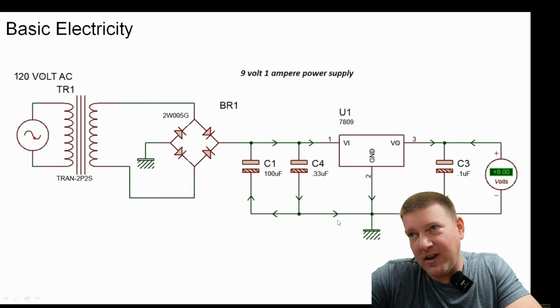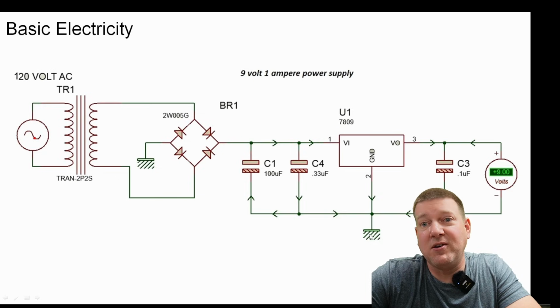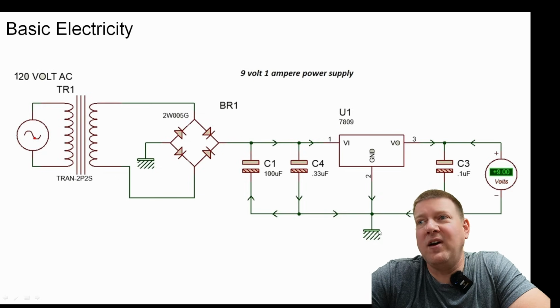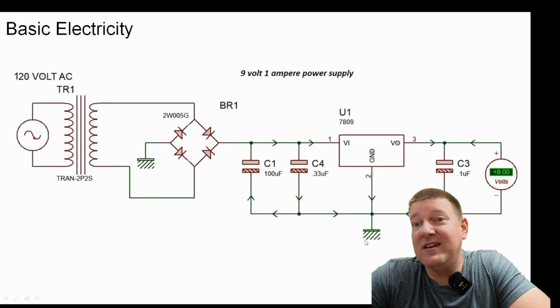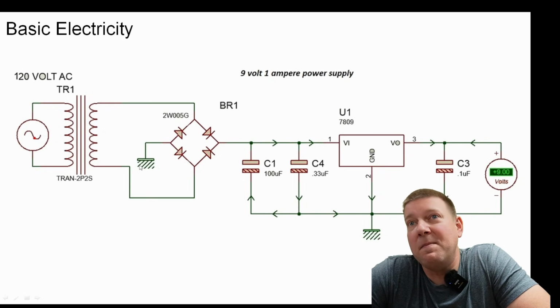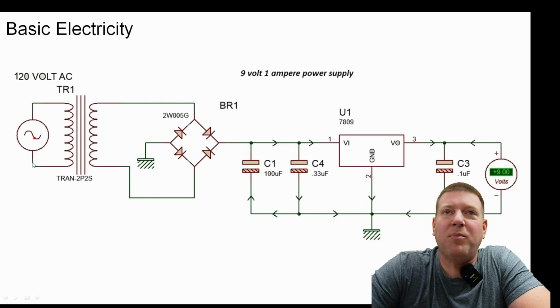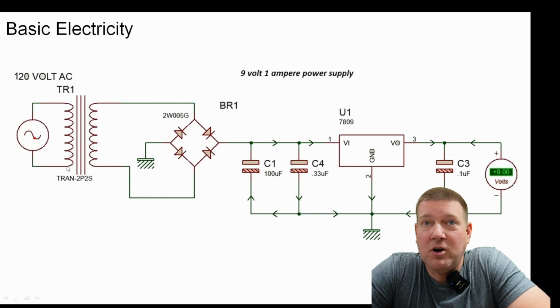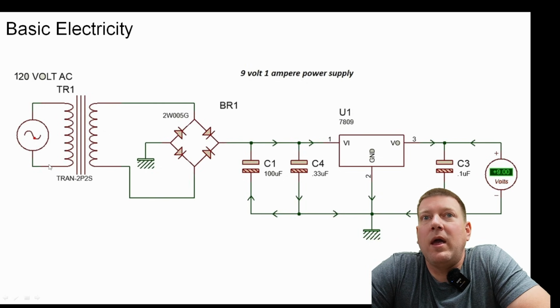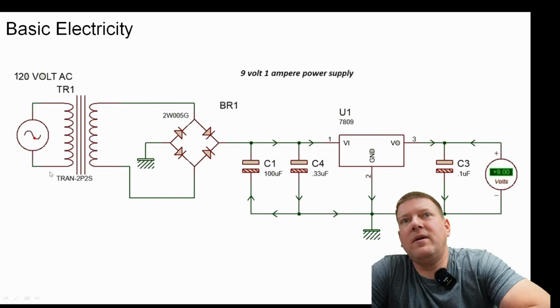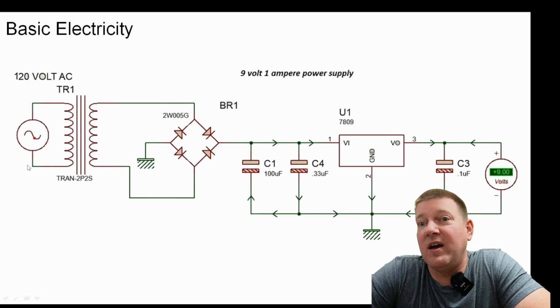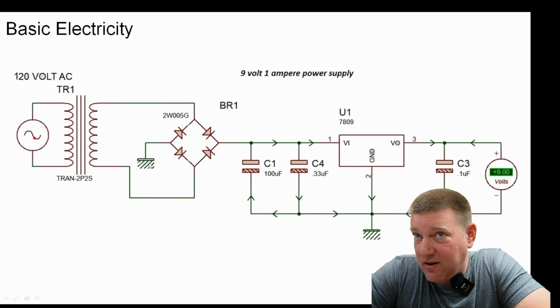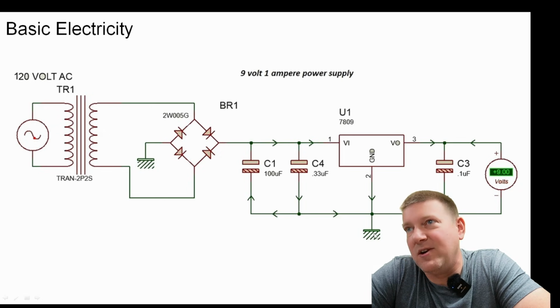Now there are other circuits, like this right here, which is definitely not a medical grade power supply, right? You can tell that because they actually have the DC side tied to ground. And you can do that. It's definitely a way of getting rid of noise, as I said earlier. So we have technically 3 ground points. One of them is going to be over here, because remember, neutral. So this is neutral, and this here is line, which is 120 volts. And down here, remember, neutral is at the same potential as ground. Okay? And then this one here is being grounded, and this one right here is also grounded.